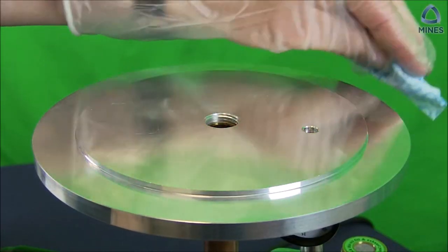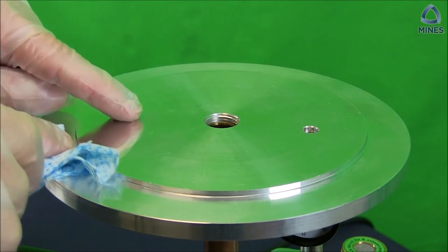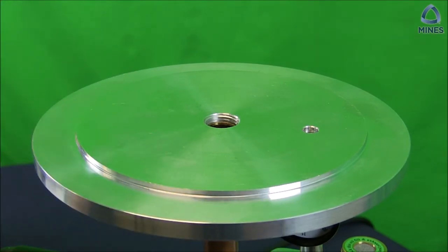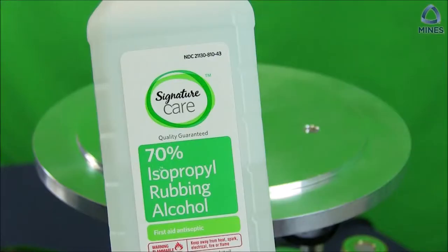Next, assure that the top of the outer machined surface region of the base plate is clean and free of hair, lint, or deep radial scratches. If the base plate needs to be cleaned, wipe it off with a lint-free cloth or, if necessary, a lint-free cloth that's been soaked in rubbing alcohol. If any deep radial scratches are observed on the aluminum surface, it may be necessary to polish the scratch using a fine abrasive media and the procedures described above.